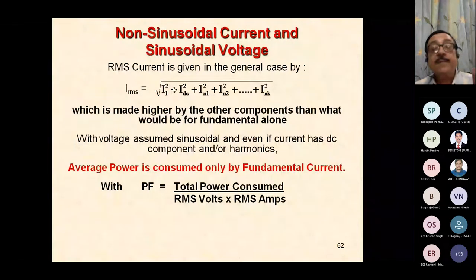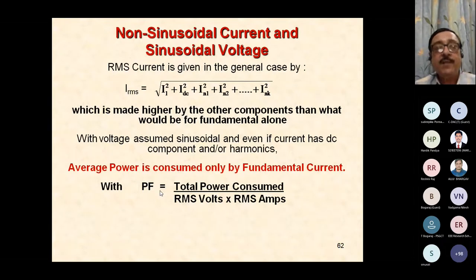case number one, when I had only fundamental current, what is the power consumed? That is at the numerator. In case number two, when fundamental current plus harmonics, what is the power consumed? It is still the same numerical value, but in this case, the RMS amps magnitude has increased. Because of this, the denominator has increased, and the power factor has reduced. So therefore, the presence of harmonics creates a reduction in power factor.